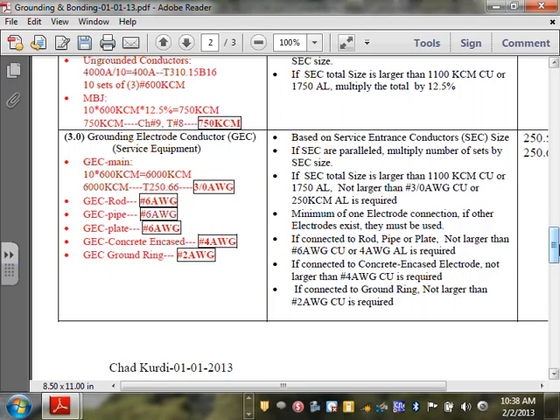So once you get to zero potential, you're at zero potential, right? Except if you have a ground fault, you want to make sure first to bond for zero potential. Then the grounding electrode system is when we bond. We bond and ground for two reasons. We bond to put everything at zero potential, because I don't want 120 between one leg and the other leg and current going right through me. That's bonding. Grounding, you ground because you want to facilitate the operation of the overcurrent protection device.